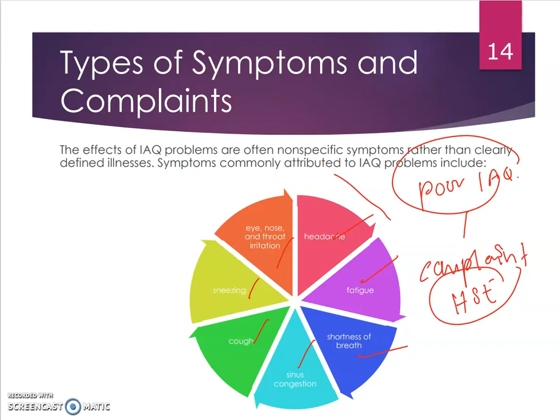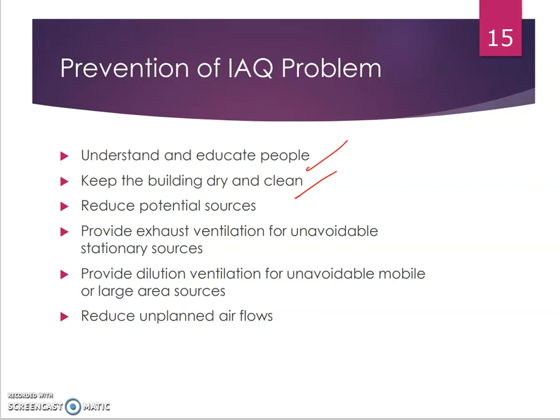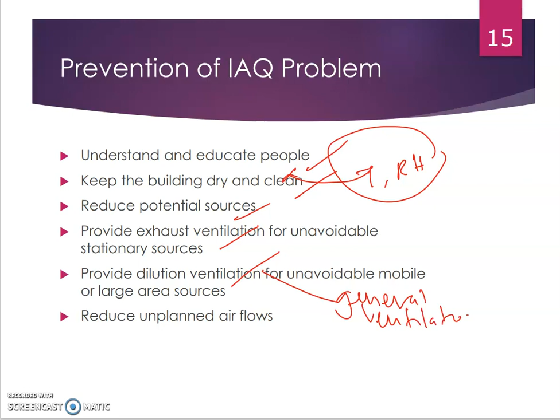Next one, what can we do to prevent indoor air quality problems? The first one, of course, we have to understand and we must educate people. Educate people in terms of what? Controlling their sources of contaminants, for example. Educate them to maintain their systems regularly. And then we also have to keep the building dry and clean by maintaining our air conditioning system. It will keep our cooling coil clean and also control the temperature and humidity inside our room. So then our building will be kept dry and reduce potential sources in that area. Any sources that will increase pollutants we must avoid, and then provide exhaust ventilation and dilution ventilation, which is what we call general ventilation. And then next, reduce unplanned airflows. We have to plan our airflow to make sure it does not carry any contaminants or problems around the indoor area.